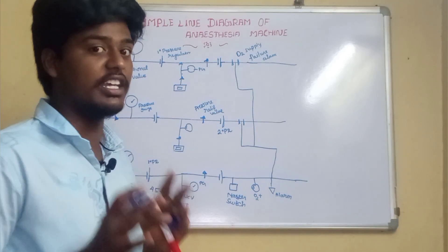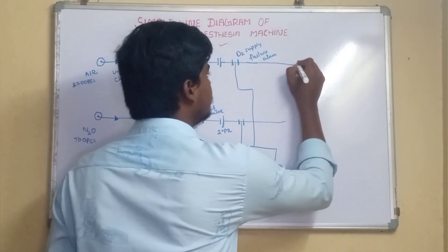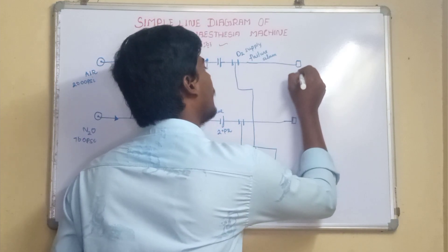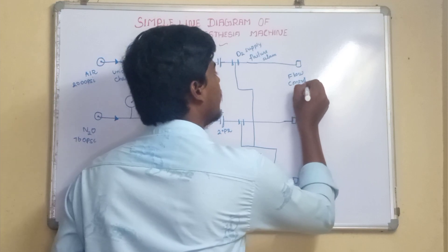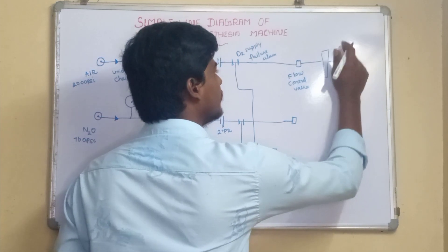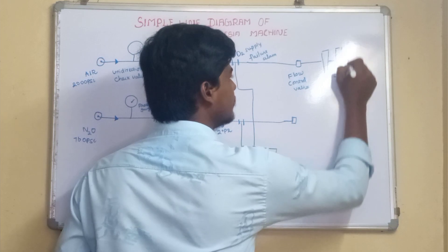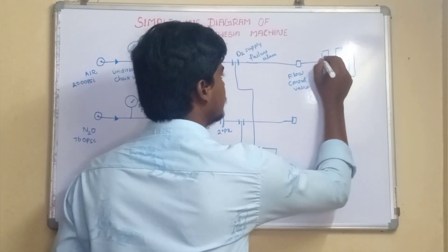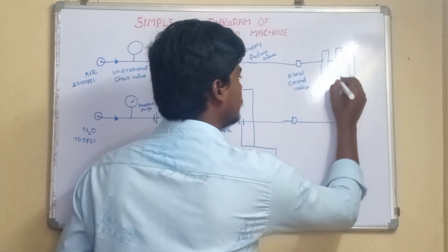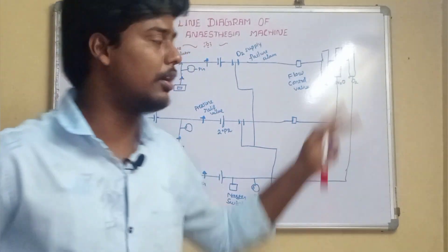The master switch and oxygen flush are independent parts of the anesthesia machine. After these, there is a flow control valve present in the air line and the other gas lines. After the flow control valve, there are flow meter assemblies: the air flow meter, the nitrous oxide flow meter, and the oxygen flow meter.